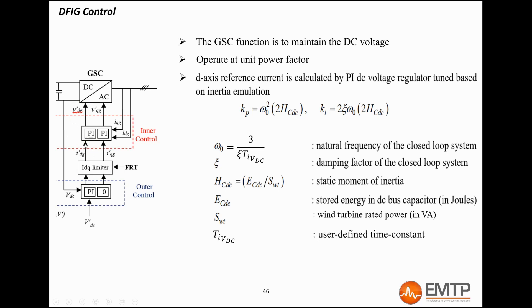Before being used by the inner loop, the current reference is limited by the id-q limiter block, so the converter does not exceed its current capabilities, which could cause hardware damage. The limiter function will be explained later on in this presentation. The gains of the outer loop PI controller for the d-axis are calculated based on the DC bus capacitance. The equations used are explained here.